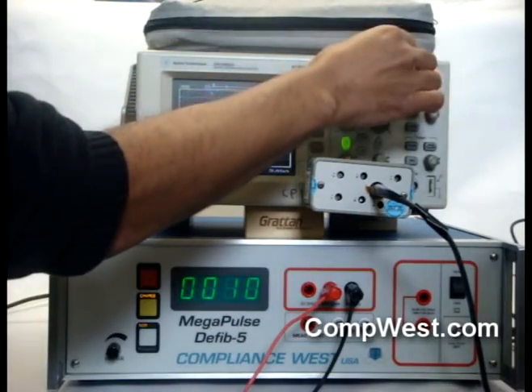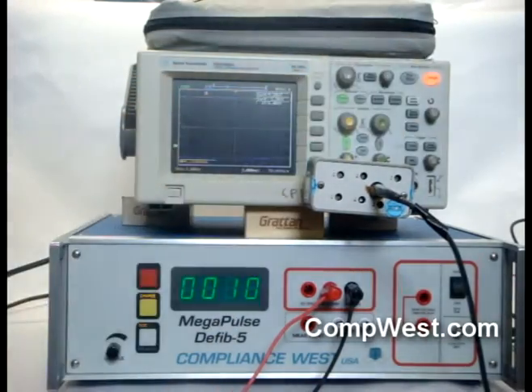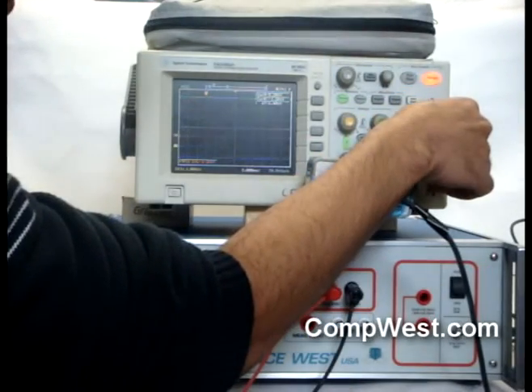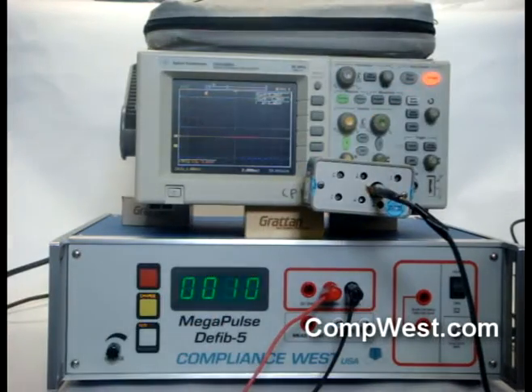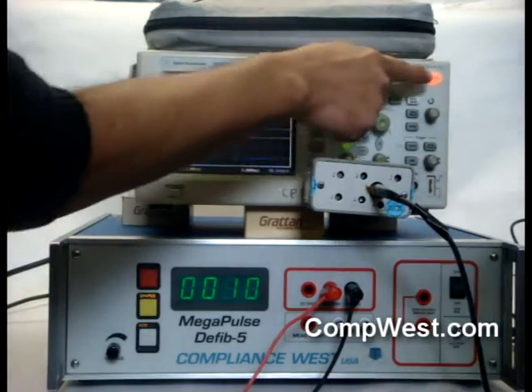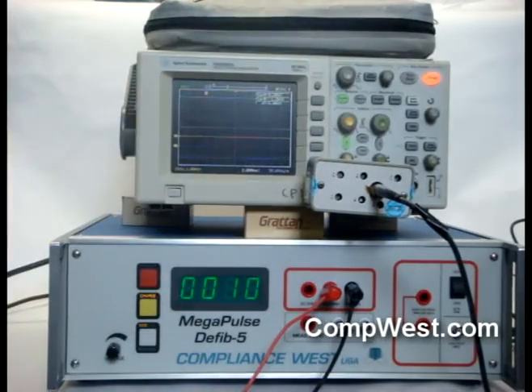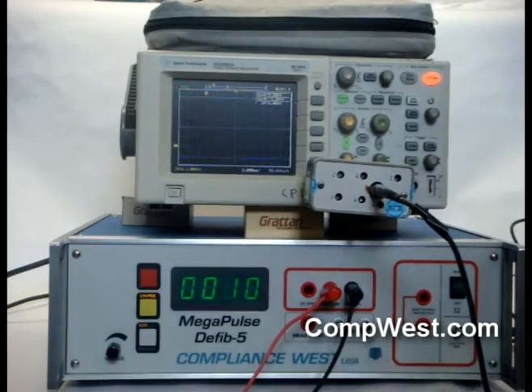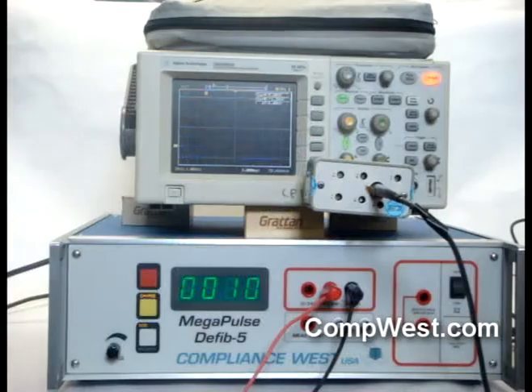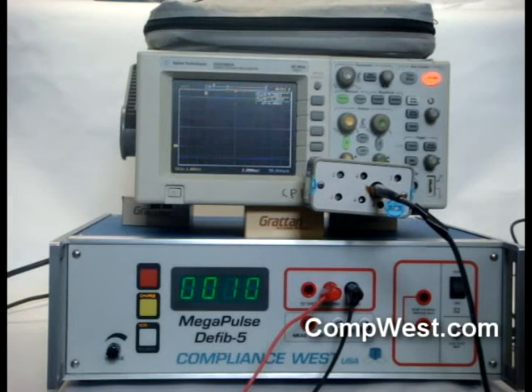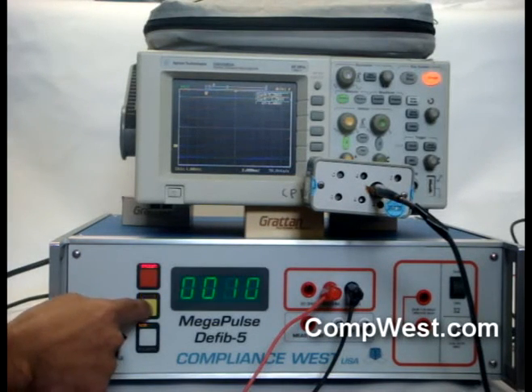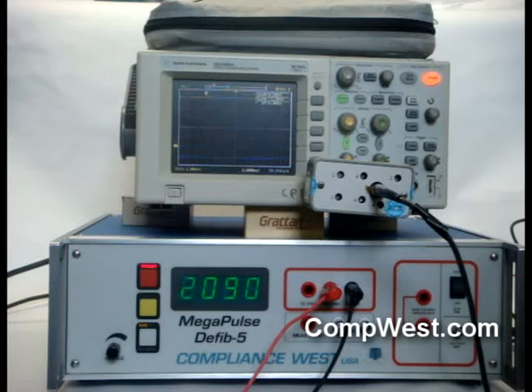Next, adjust the trigger level of the scope to approximately 1 kV. Then, set up the scope so it will capture a single waveform. In the case of the DSO3062A, the single button is pressed. Press charge on the Megapulse Defib-5 and wait until the input voltage shown on the front panel display is 5,000 volts.